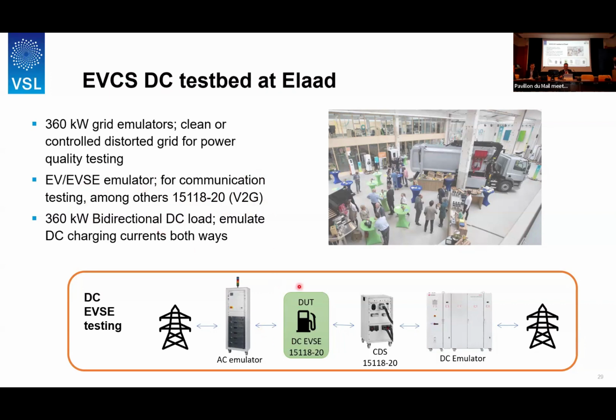Schematically, it looks like this. We have the EV charging station here, and we have the AC grid emulator here. That's of course connected to the real grid, so it more or less cleans the grid, so to say. Then there's this communication device in between, and here is the DC grid emulator to absorb the energy and feed it back into the grid, such that the energy is not really dissipated as heat. Because 360 kilowatts is quite a lot if you are heating your laboratory in that case.